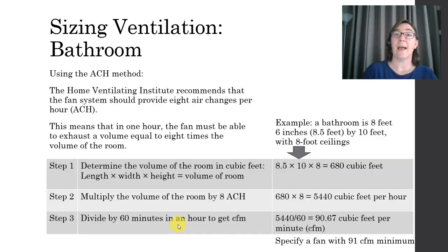You can also size the ventilation system for your bathroom using the ACH method. And this is based on, again, the recommendation that you provide 8 air changes per hour for your bathroom. And this means that in 1 hour, the fan has to exhaust a volume equal to 8 times the volume of the room. All right, so here's what we do.